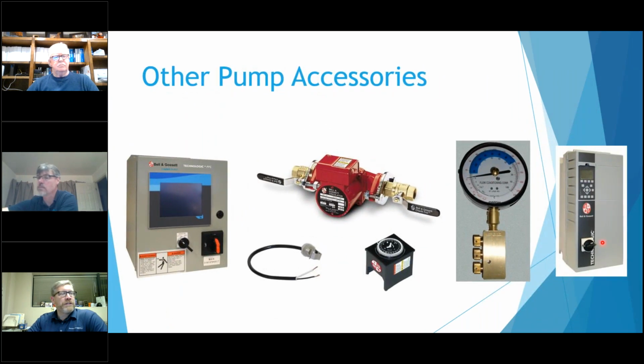Some of the other accessories, of course, you see a lot of VFDs out there on these systems. This is a little control panel for the pump that you can have. A lot of these, especially retrofits, come with sensorless technology. You see a lot of the sensorless come in with retrofits because they don't have a system there, and they want to have a way to control the pump. Some of this will take care of that. There's a lot of built-in capabilities on drives these days where you don't need a control panel. It's all done by the drive.